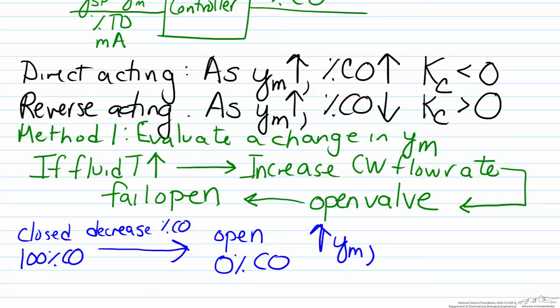Thus, as we have an increase in the value of the measured variable, that is going to require a decrease in the percent controller output. So what that means is our final decision here would be to have a reverse acting controller.